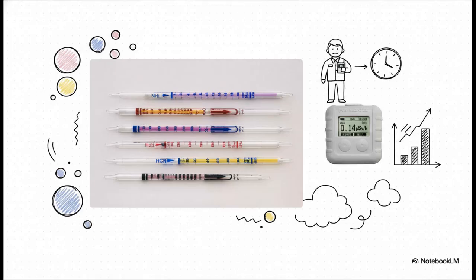And here we contrast your essential toolkit. On one hand, we've got detector tubes. These are brilliant for immediate on-site chemicals spot checking. They contain a chemical that physically reacts and changes color if a suspected contaminant is present right then and there. On the other hand, we have dosimeters. These are worn directly by the worker and continuously track their exposure throughout the entire shift. They literally collect the raw data you need for those time-weighted averages we just calculated.